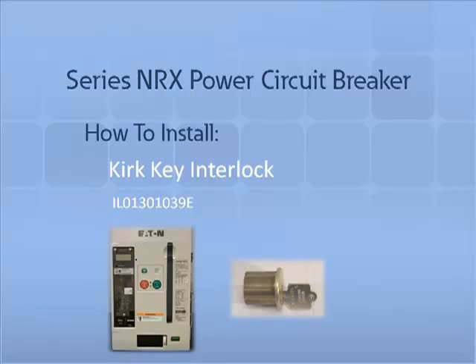Thank you for joining us for another Series NRX accessory tutorial video. In this video we will demonstrate how to install and remove a Kirk key interlock. The Kirk key interlock is an additional safety locking feature that provides controlled operation of the circuit breaker. The key interlock secures the breaker in the off position and without a key the breaker cannot be turned on.